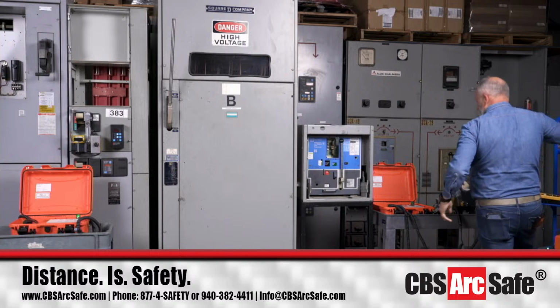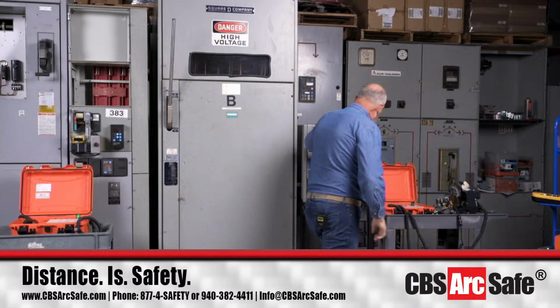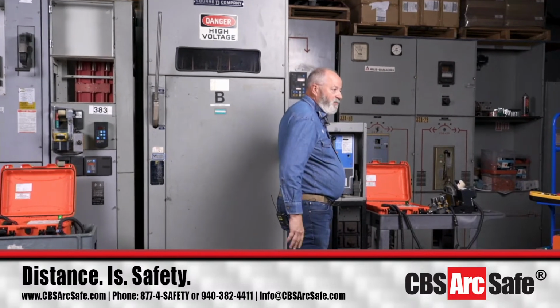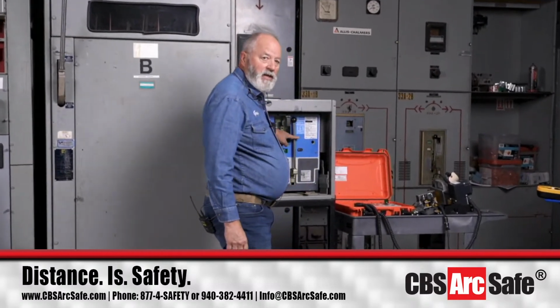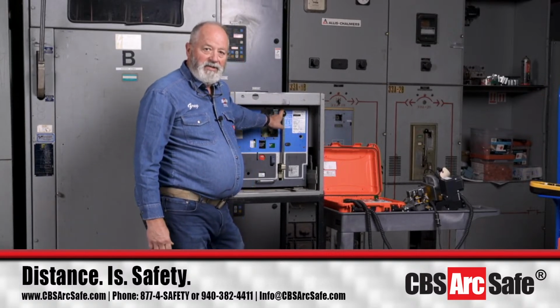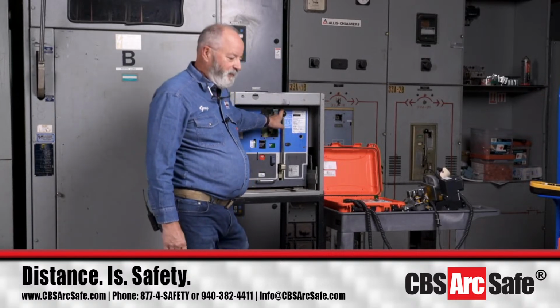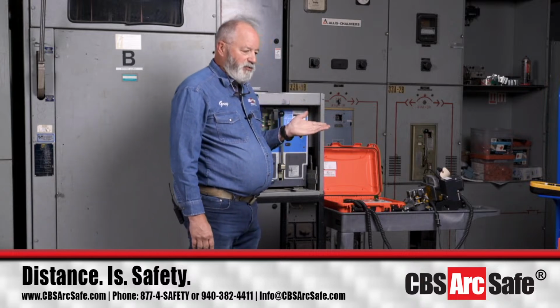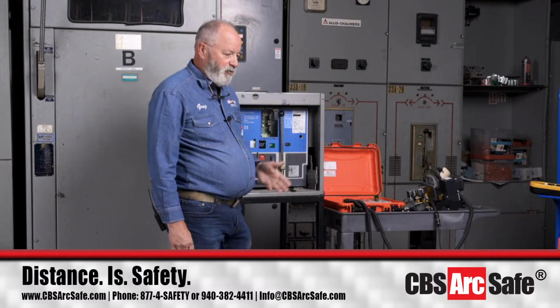A short arm DS breaker is an electrically operated one, and an arm stops right about here. The manually operated one has the longer arm, and it takes 1 stroke, while the electrically operated one takes 9 strokes. Okay, and I went to a facility one day down in Bay St. Louis, Mississippi.